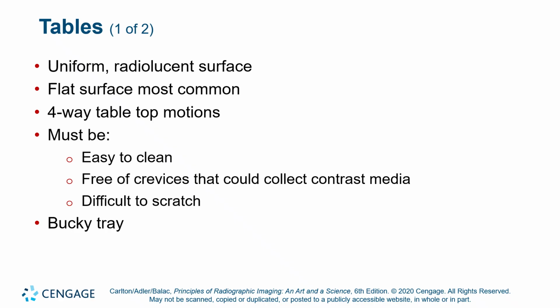Some of them will be left on the textured surface. So let's just have a smooth surface, no scratches, no stippling, no porous areas, free of crevices that could collect contrast media and patient sweat and other body fluids.